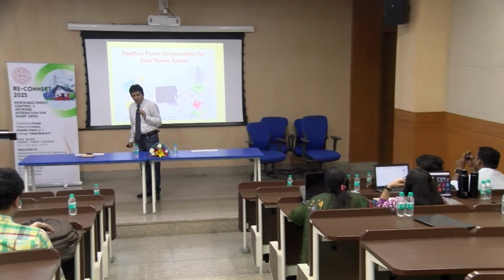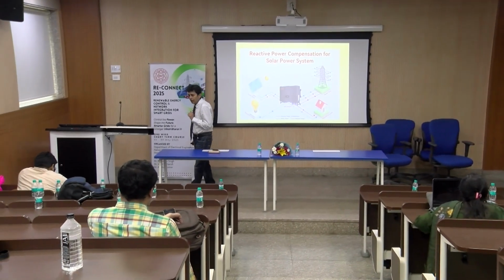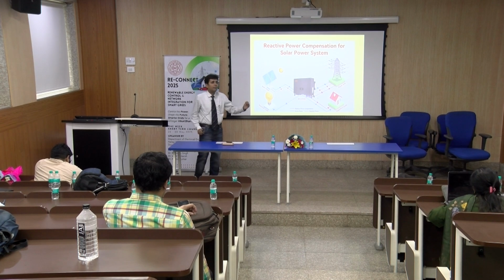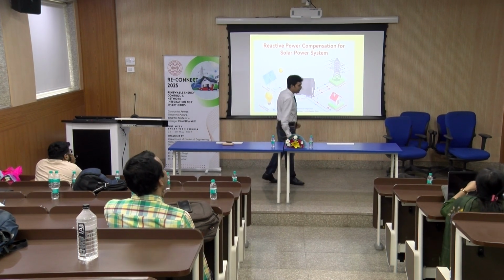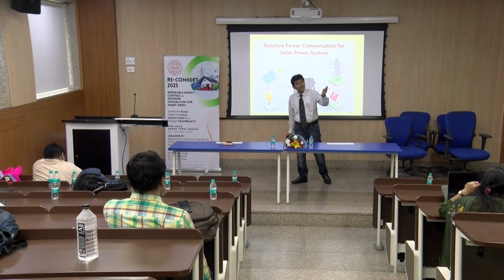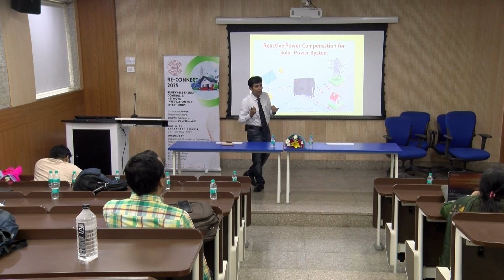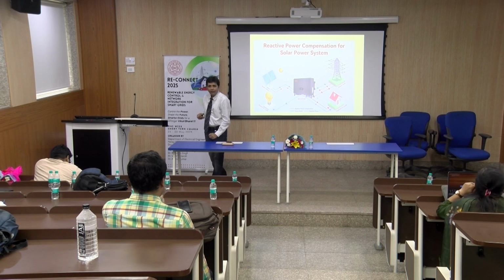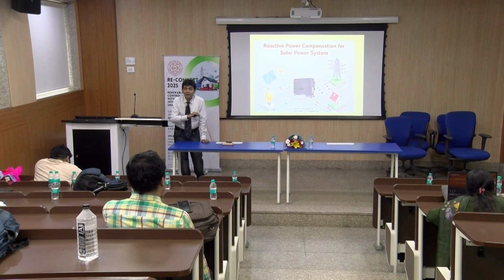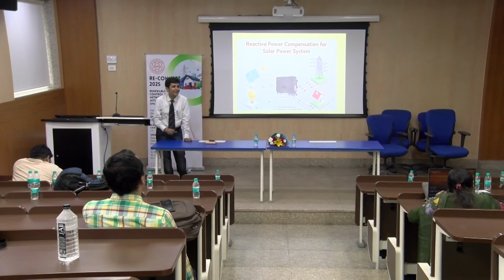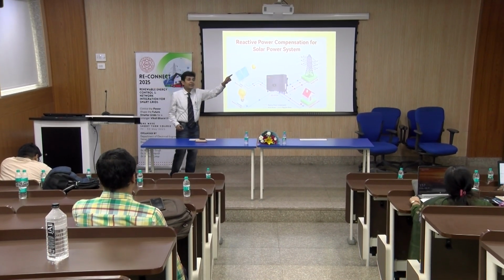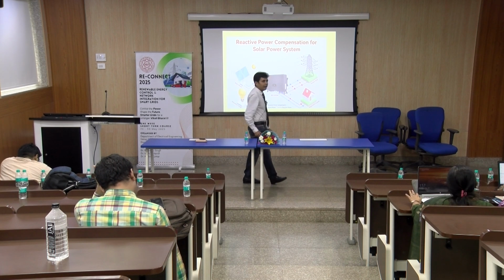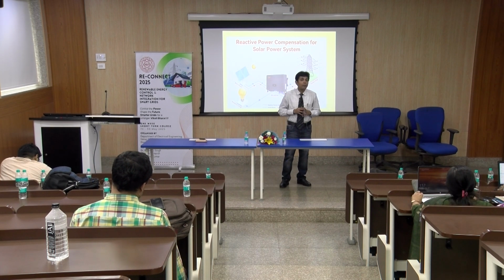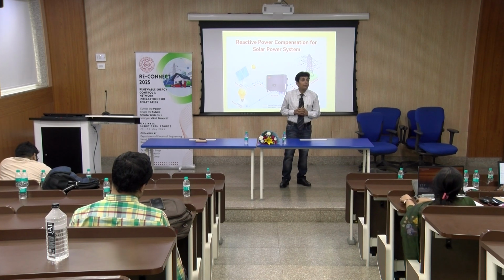What happens to run your load? You need two powers. One is your active power, and the second is the reactive power. You have installed solar PV of 5 kilowatt. That means the active power requirement from the distribution transformer where I was getting the power has reduced by 50%. In case your inverter fails to support the reactive power requirement, that will still be coming from the DT you are connected with. When the DT produces more reactive power, it causes heating. There will be more losses in the system.